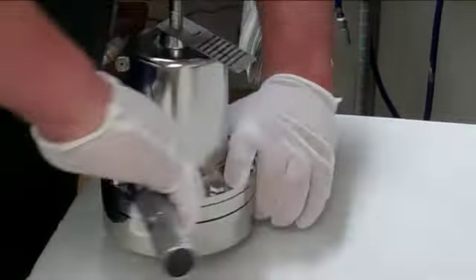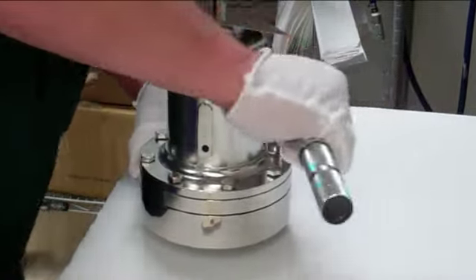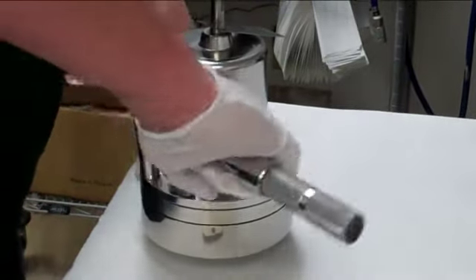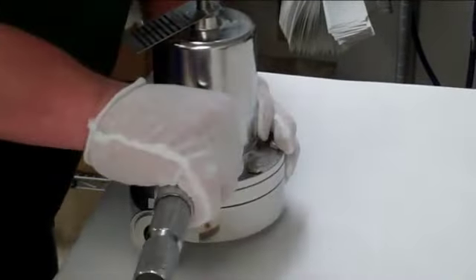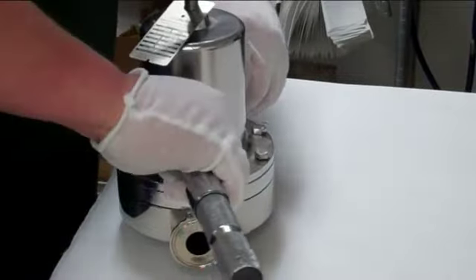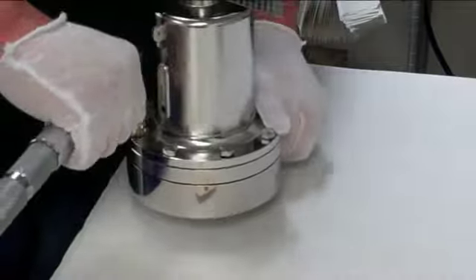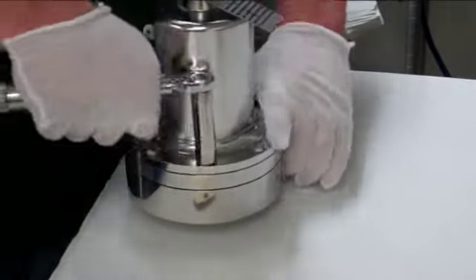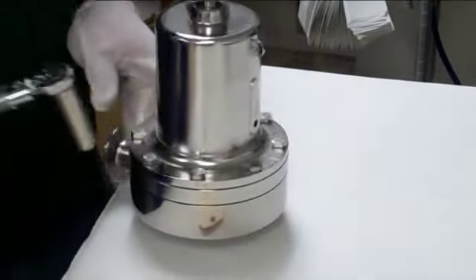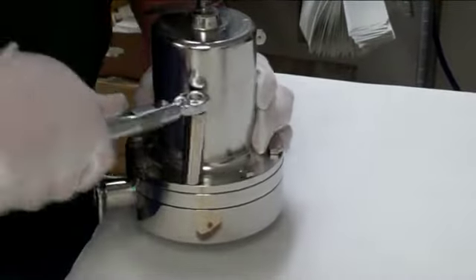Now, take your torque wrench, which is at 200 inch pounds, and start cross-torquing each individual bolt. Double check every bolt to make sure all bolts have been cross-torqued.